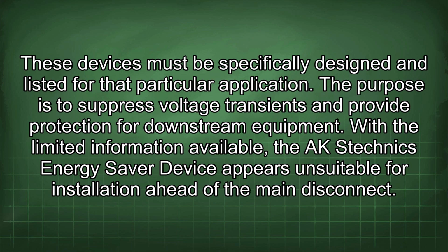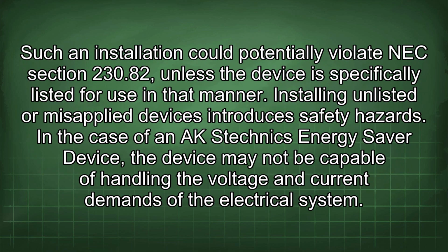The purpose is to suppress voltage transients and provide protection for downstream equipment. With the limited information available, the AK Stechnics Energy Saver device appears unsuitable for installation ahead of the main disconnect. Such an installation could potentially violate NEC Section 230.82 unless the device is specifically listed for use in that manner. Installing unlisted or misapplied devices introduces safety hazards.